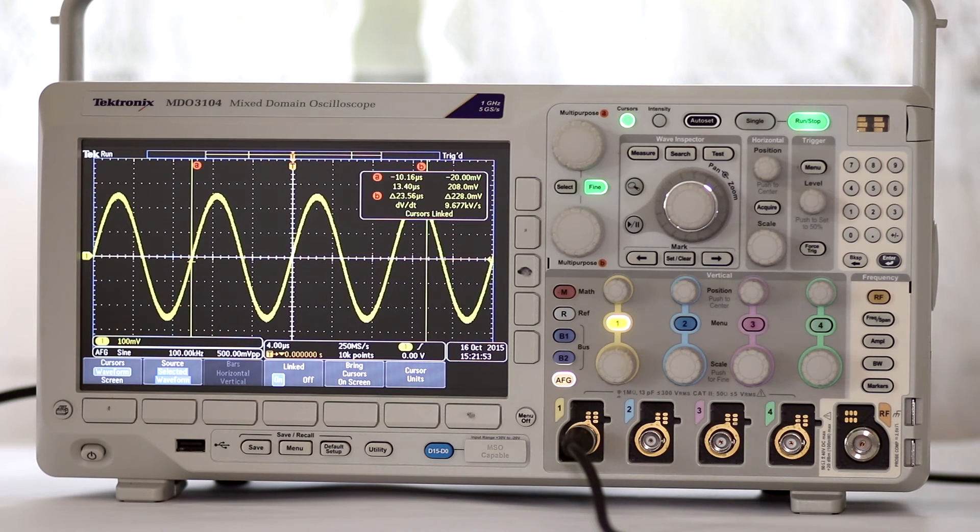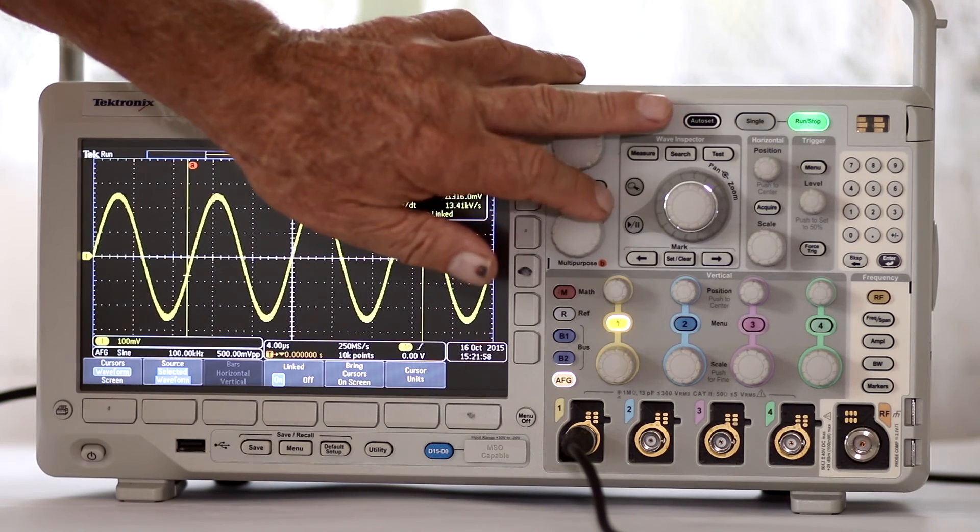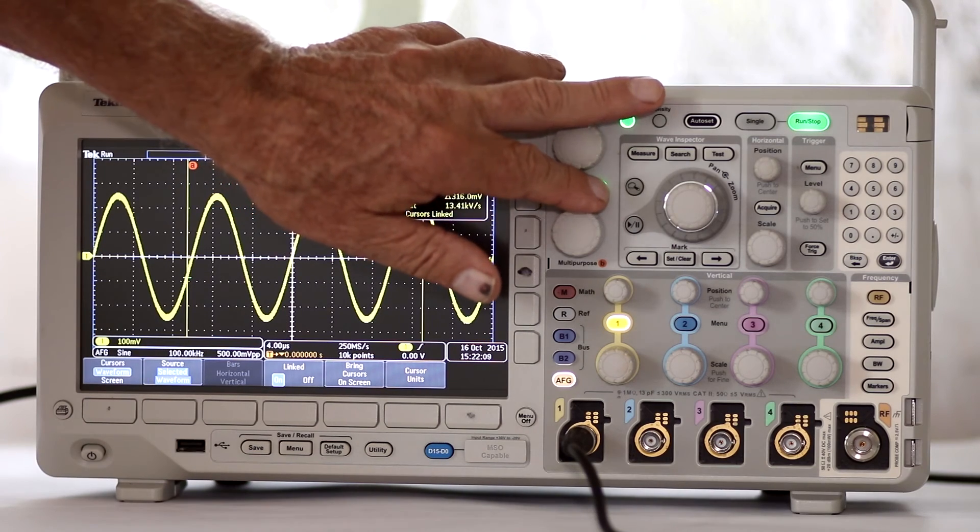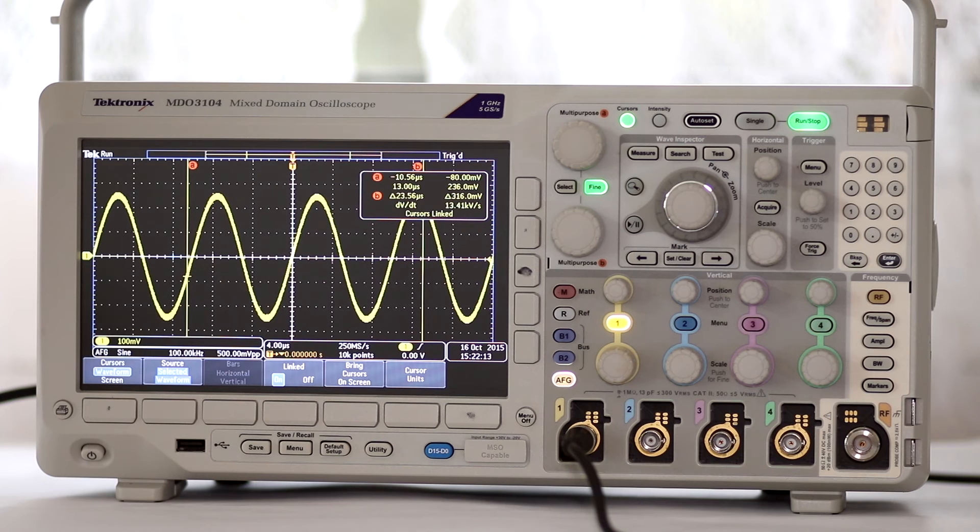To the right of the select button is the fine button. Pressing it repeatedly toggles between fine and coarse, which relates to the sensitivity of multipurpose knobs A and B. When you have a long distance to go, coarse enables the adjustments to be made more quickly. But when working with cursors, fine is usually the way to go.